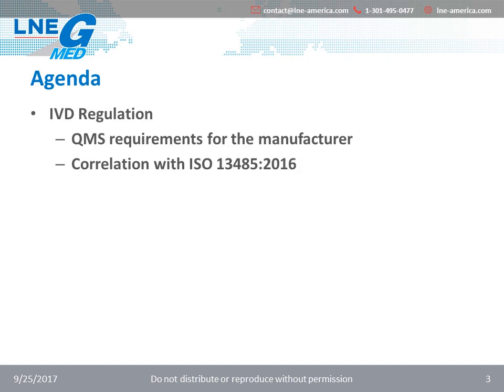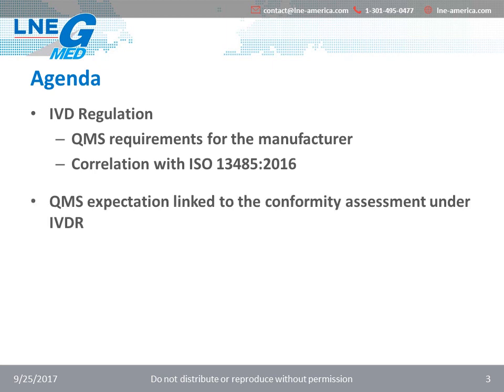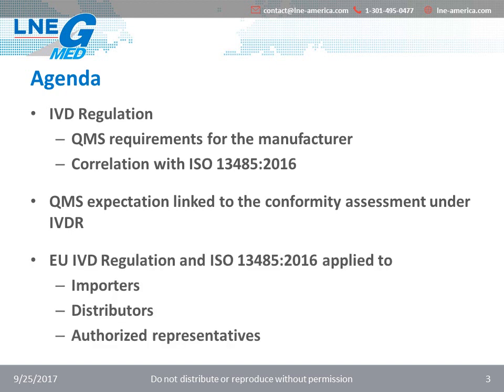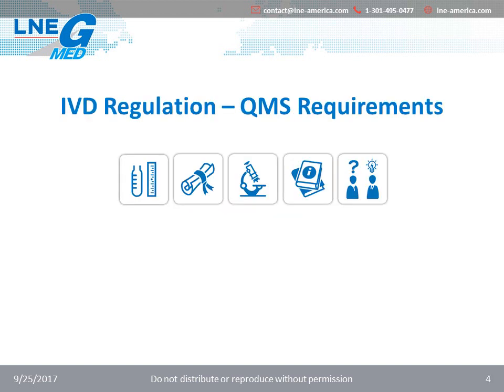Throughout this webinar, we will first explore the QMS requirements for manufacturers that are introduced by the new IVDR and the correlation with the requirement of the ISO 13485:2016 standard. Then, we will review the QMS expectation linked to the conformity assessment under the IVDR. And then finally, we will see how the ISO 13485:2016 does apply and the impact of the regulation on this application for importers, distributors, and authorized representatives. So, without further ado, let's explore the QMS requirement introduced by the new IVDR.